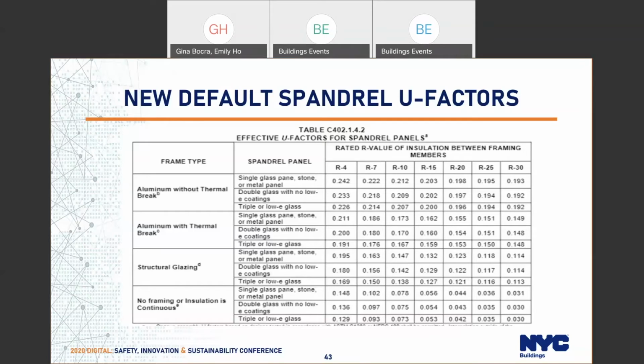And as I mentioned, if you go below R4, then it's essentially a non-insulated panel, and you have to do a THERM analysis for that panel too. So you would use this default U-factor for an assembly that is described, again, in the first two columns as your default value. If you have an assembly that is described here, but for whatever reason you feel is performing much better than the table, again, you would use a THERM analysis to show us how you came to a different U-factor. Hopefully, this will streamline review both for our applicants and for our energy code plan examiners and help us get through these spandrel reviews faster.